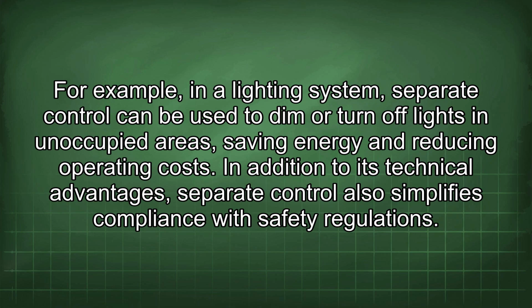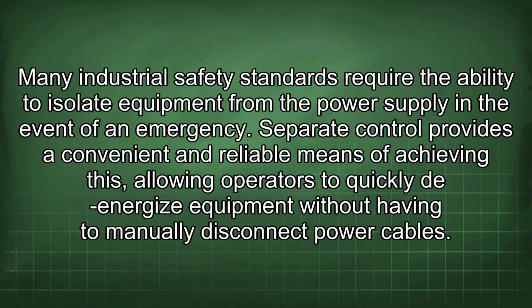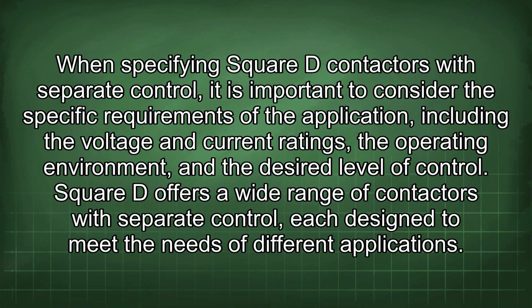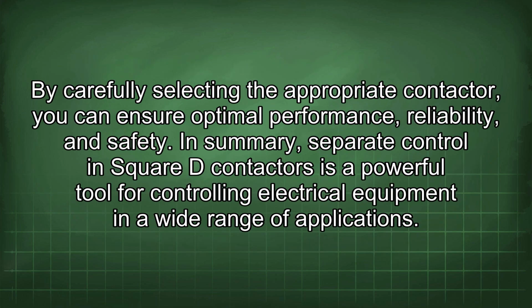In addition to its technical advantages, separate control also simplifies compliance with safety regulations. Many industrial safety standards require the ability to isolate equipment from the power supply in the event of an emergency. Separate control provides a convenient and reliable means of achieving this, allowing operators to quickly de-energize equipment without having to manually disconnect power cables. When specifying Square D contactors with separate control, it is important to consider the specific requirements of the application, including the voltage and current ratings, the operating environment, and the desired level of control. Square D offers a wide range of contactors with separate control, each designed to meet the needs of different applications. By carefully selecting the appropriate contactor, you can ensure optimal performance, reliability, and safety.